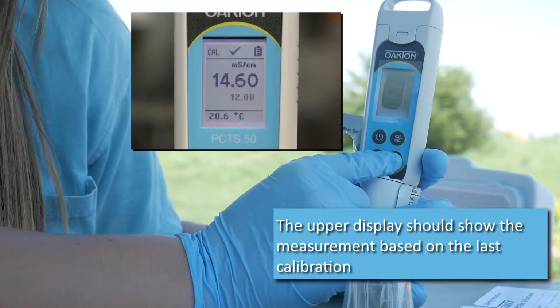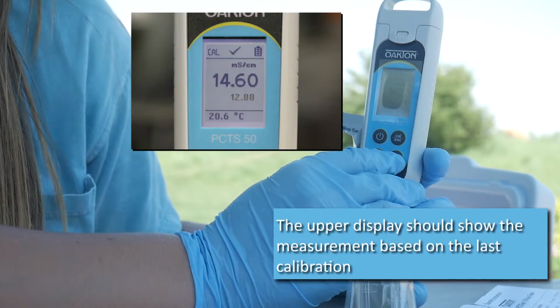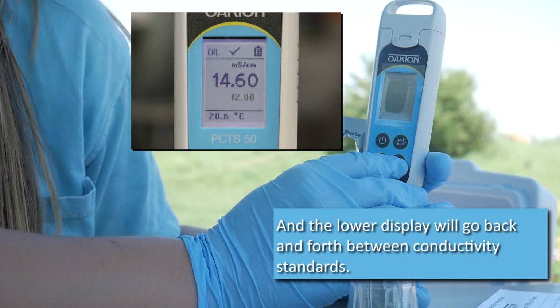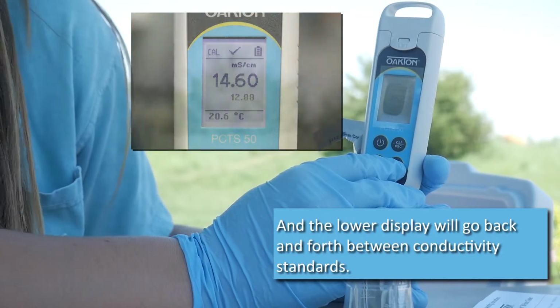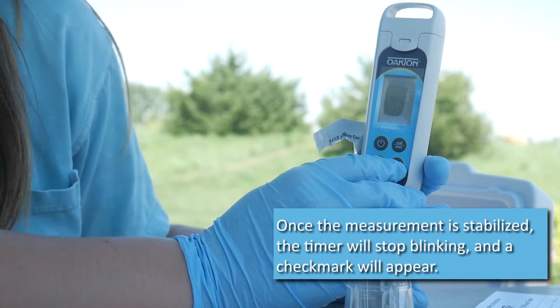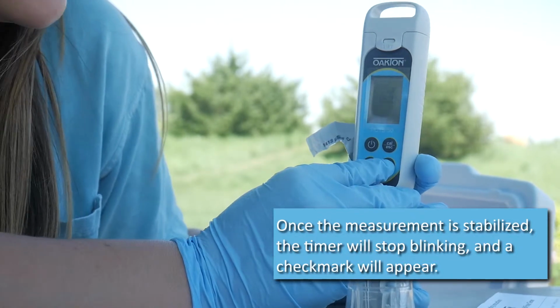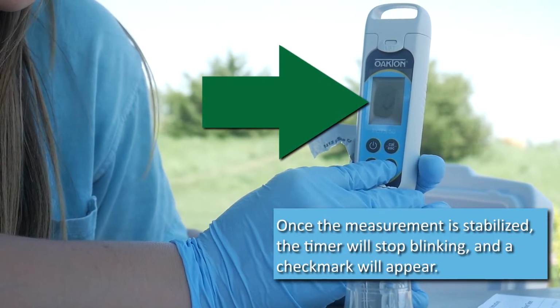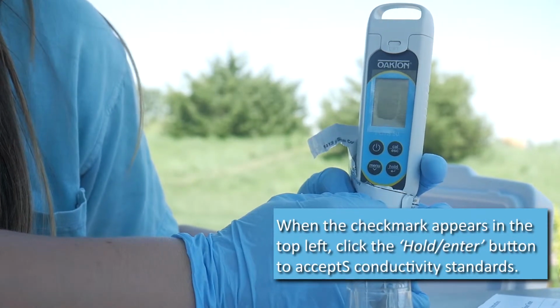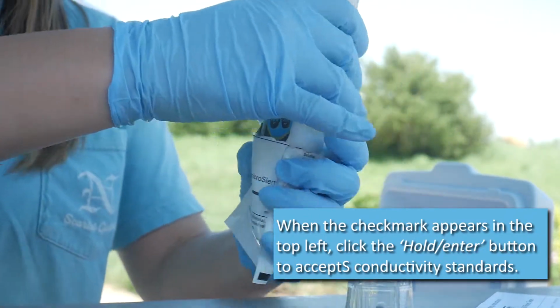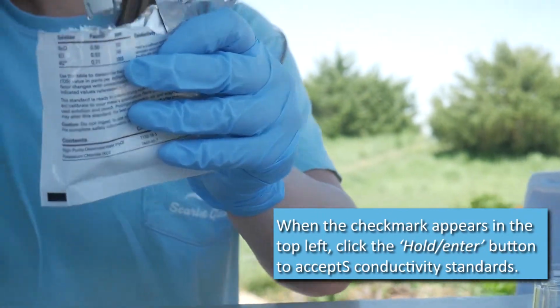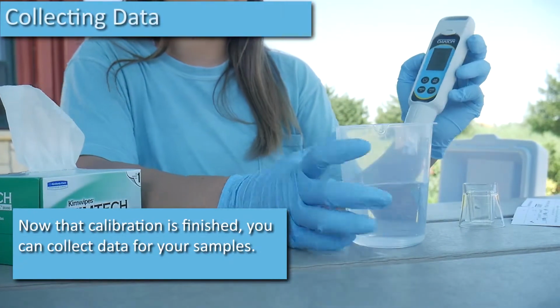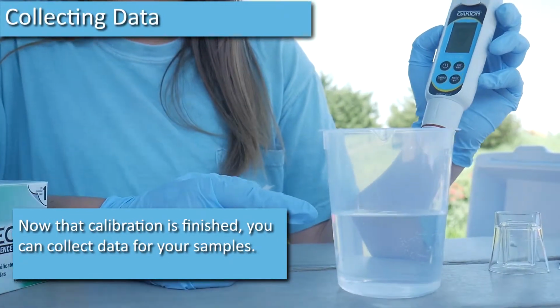The upper display should show the measurement based on the last calibration, and the lower display will go back and forth between conductivity standards. Once the measurement is stabilized, the timer will stop blinking and a checkmark will appear. When the checkmark appears in the top left, click the Hold Enter button to accept conductivity standards. Now that calibration is finished, you can collect data for your samples.